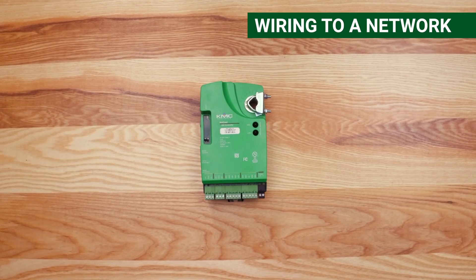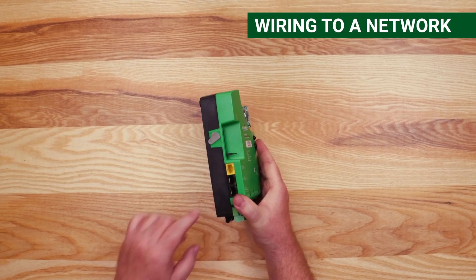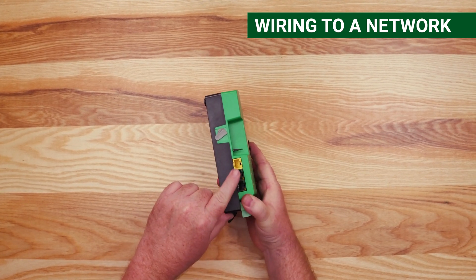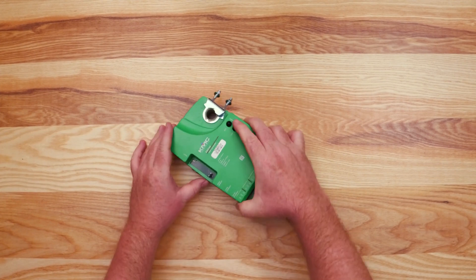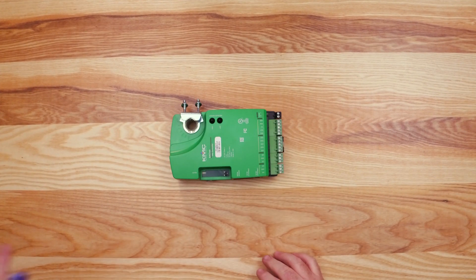In this video, let's cover wiring to a network and the inputs. Let's begin with the wiring of the controller to a network. This BAC 9000 series controller connects to the network via BACnet over IP. This model includes two Ethernet ports with a built-in switch, allowing for easy daisy chaining on the network.